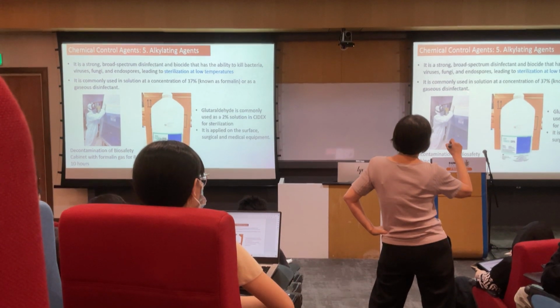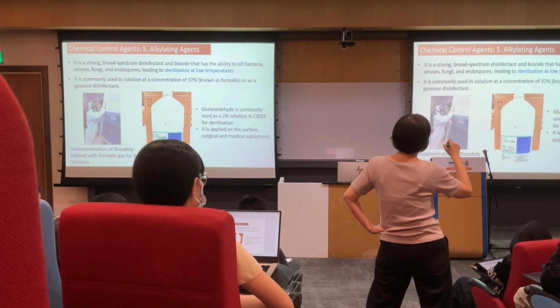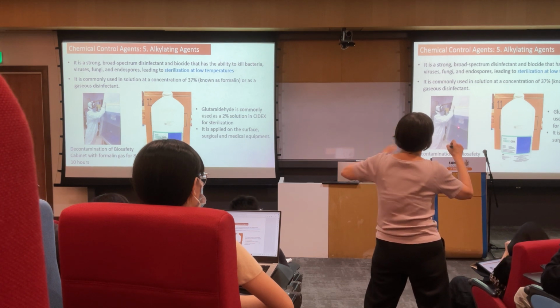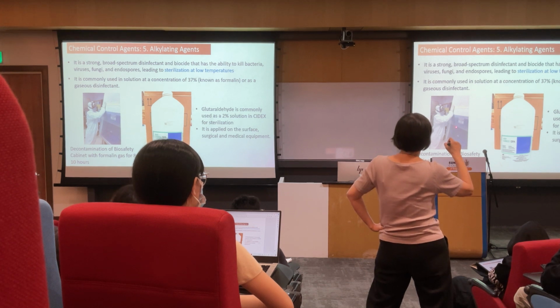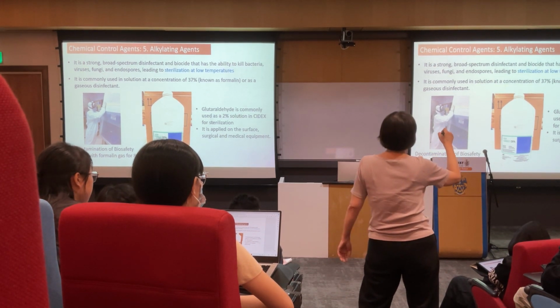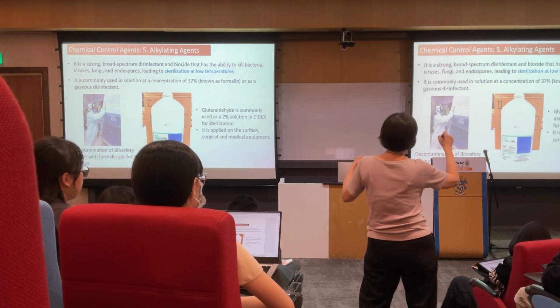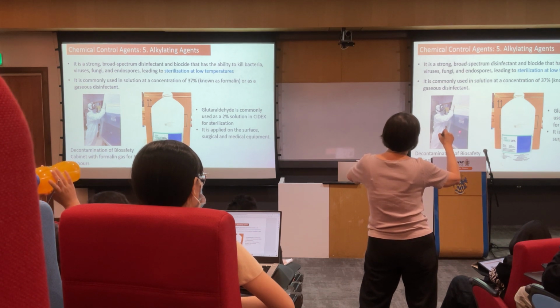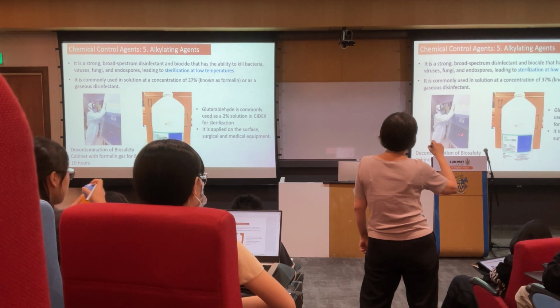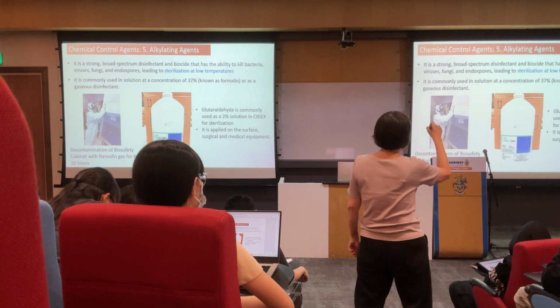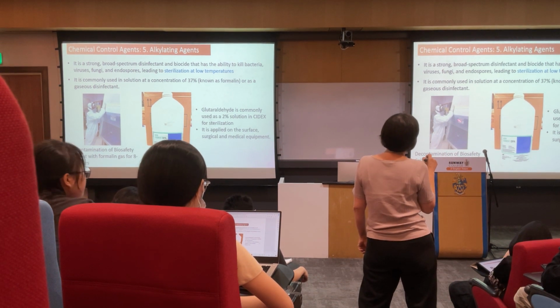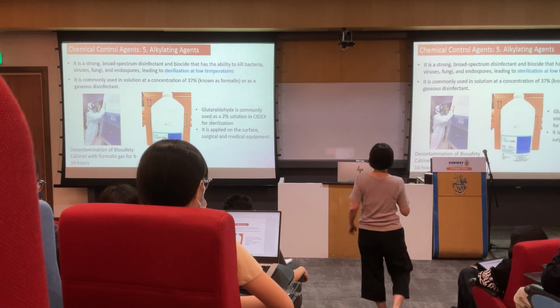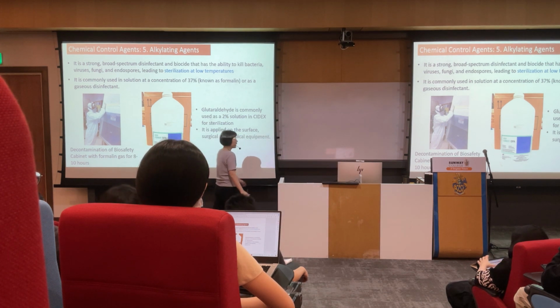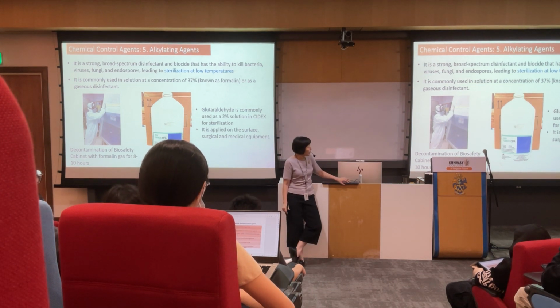And this one, they actually use to decontaminate the biosafety cabinet. Of course, normally we keep the biosafety cabinet clean, we apply the UV light, we wipe with ethanol, and normally they do not recommend wiping with ethanol. So we clean it constantly, but once or twice a year, you will ask somebody to come over to use the gas. I think they use formalin gas. They wrap the whole cabinet and then insert the gas inside, and the gas will go everywhere in the cabinet. I think they leave it for half a day. After that, it is very, very clean. So you need to ask the company people to come here to do that. I think I've seen it once. It is actually a very powerful agent.